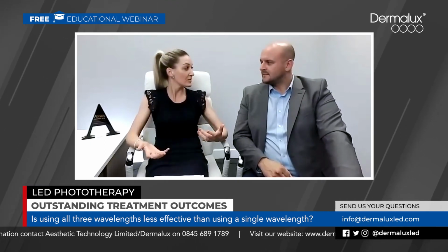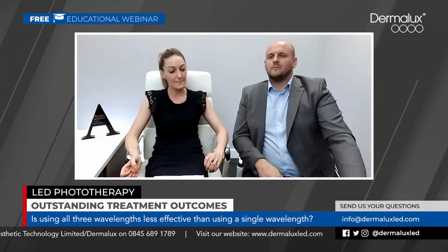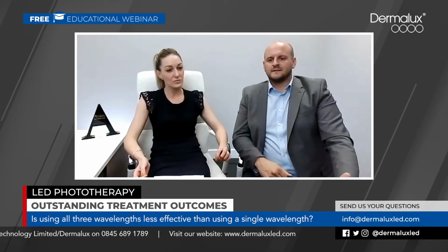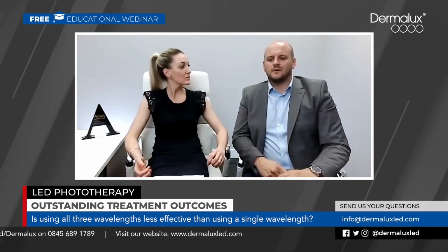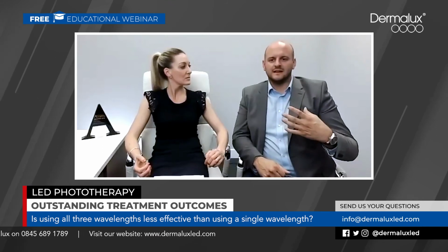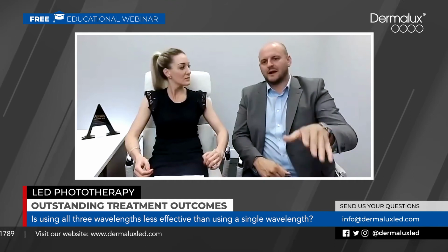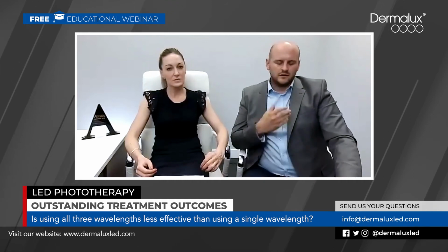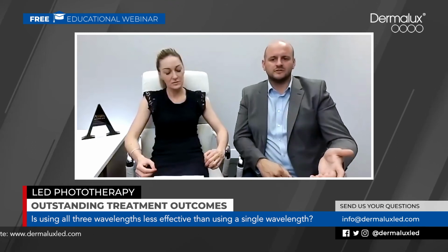You're just delivering more optical power, aren't you, with all 3 wavelengths on together. There is also a middle ground, where there are devices on the market that actually pulse the LED. With some devices you can see the LEDs physically changing, so they look like they're increasing and decreasing in power over the course of the treatment. Other devices use pulse width modulation, so they're pulsing the LED at a particular rate such that the eye doesn't see that they're being pulsed, but the skin does.